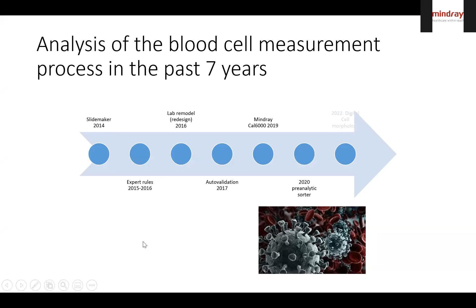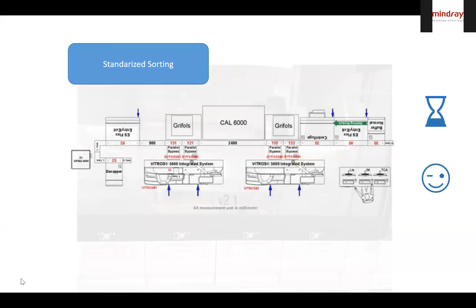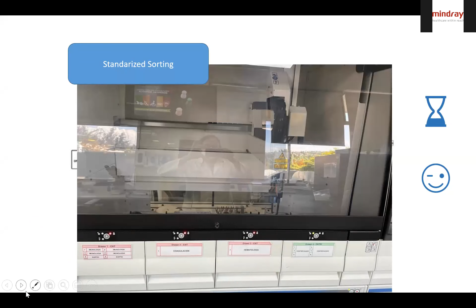This is a scheme of the pre-analytic automated system that has two entries, and we use this one, the second one. The second one we use to sort all the samples that are not connected to the automated chain of distribution, and one of them is the CAL 6000. This is the sorter and this is the tray that we use to put all the lavender cap tubes, so they are sorted and put directly in the racks of the analyzer to be taken and put in the equipment. This saves time and also makes the people not have to be aware of the sorting, and makes it easier for the routine.